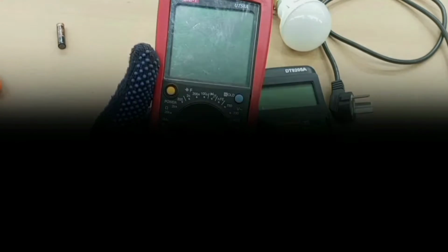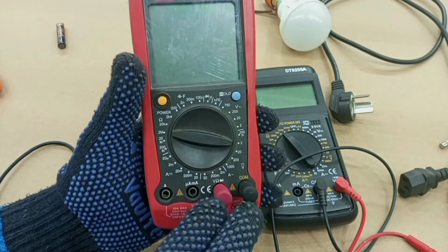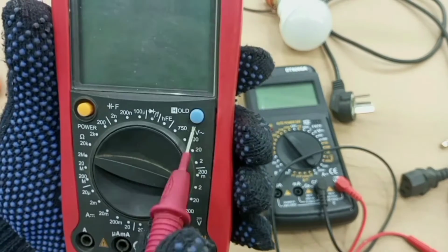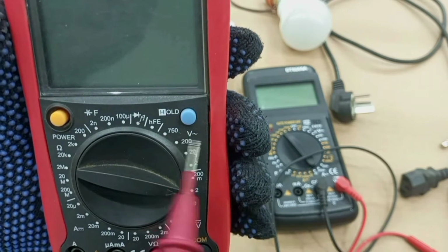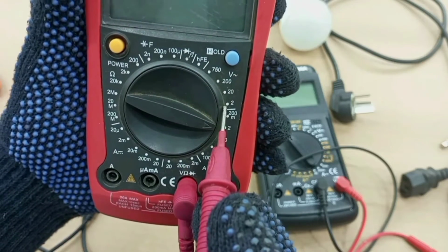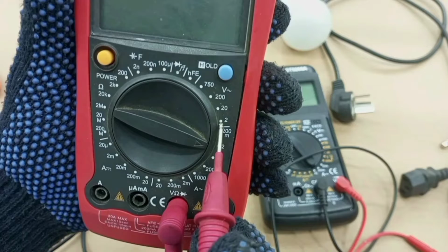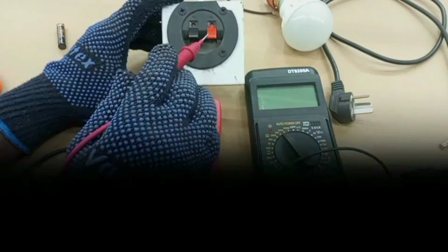All right, so the next measurement we are going to take is AC voltage. And when measuring alternating voltage, the probes will still remain where they are, but then we'll have to change to AC voltage. This sign represents AC voltage. And in that column also, we can measure any voltage between 2 volts up to 750 volts. Now, the supply voltage I'm expecting here is 230 volts.